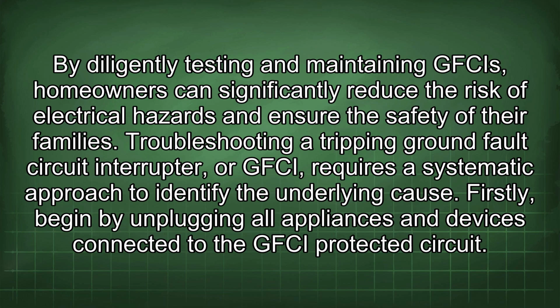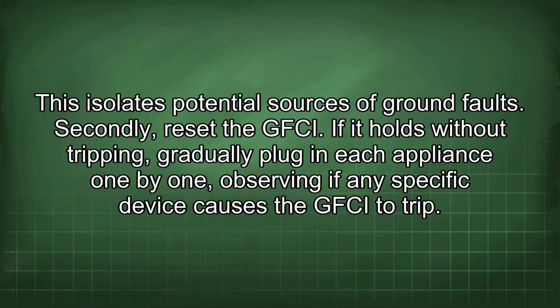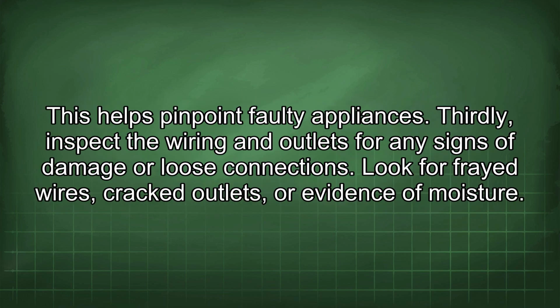their families. Troubleshooting a tripping ground fault circuit interrupter, or GFCI, requires a systematic approach to identify the underlying cause. Firstly, begin by unplugging all appliances and devices connected to the GFCI protected circuit. This isolates potential sources of ground faults. Secondly, reset the GFCI. If it holds without tripping, gradually plug in each appliance one by one, observing if any specific device causes the GFCI to trip. This helps pinpoint faulty appliances.